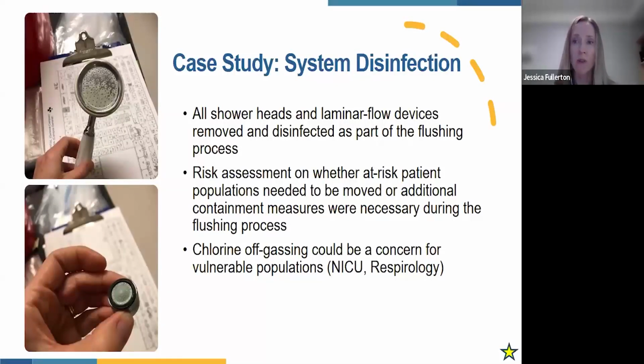Chlorine off-gassing was also a consideration, brought up by our occupational health and safety physicians. It can be a concern for vulnerable populations such as respirology and NICU. We had carbon-filtered construction air handling units ready in case off-gassing became a problem. Thankfully it was not, but it's certainly something to consider.